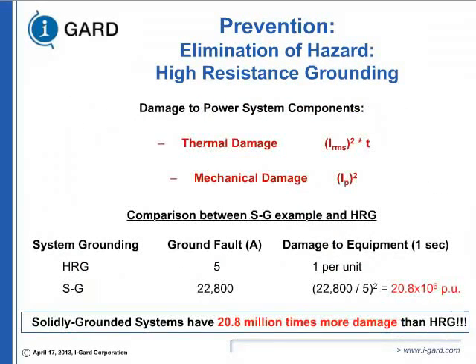Now, how does it help? Thermal damage is based on I squared T. The current is flowing for a time, the square of that current multiplied by T, which is the time it takes to clear a fault. So if you have solid grounding, and just for discussion's sake, you have a 22,800 amp ground fault, as opposed to limiting it to a 5 amp ground fault by high resistance grounding, if you compare that, the damage potential has been reduced by over 20 million times.